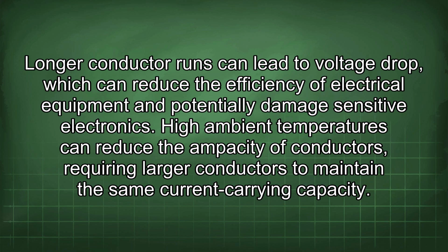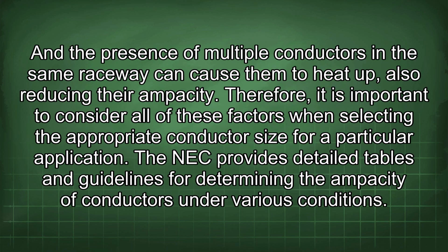High ambient temperatures can reduce the ampacity of conductors, requiring larger conductors to maintain the same current carrying capacity, and the presence of multiple conductors in the same raceway can cause them to heat up, also reducing their ampacity. Therefore, it is important to consider all of these factors when selecting the appropriate conductor size for a particular application.